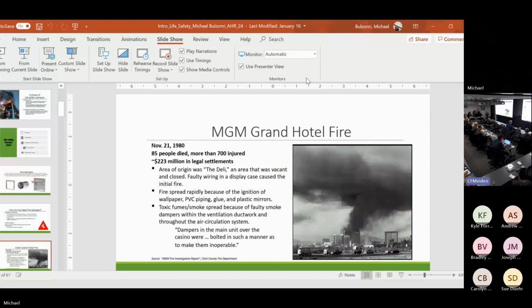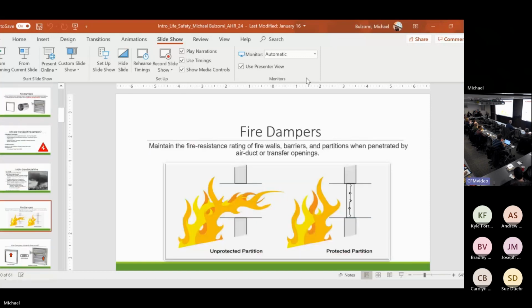But this would have been caught if there was testing and inspecting requirements in the building code, and there were not. So Clark County adopted inspection and testing and maintenance requirements of dampers to prevent this from happening, and that's the whole purpose of testing our dampers. We'll go into testing in a little bit. So here we're just showing a protected partition versus an unprotected partition.